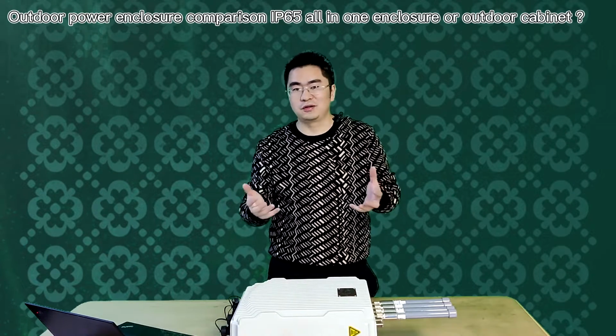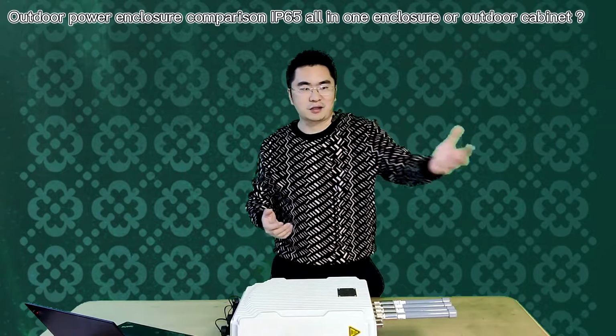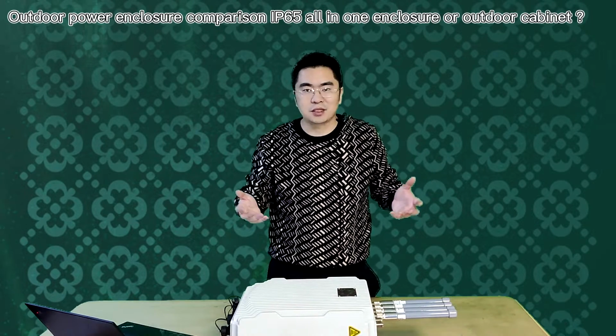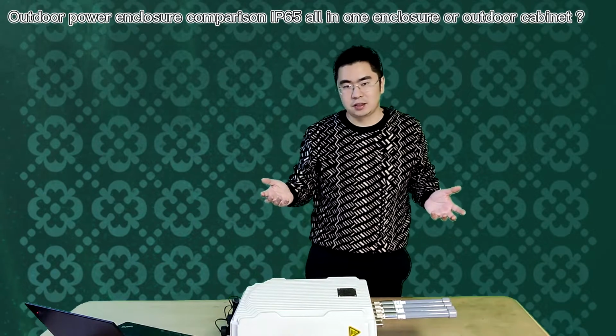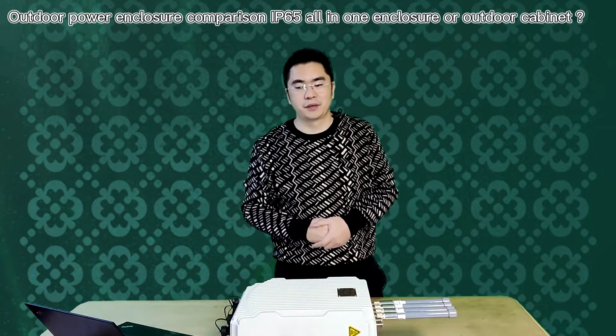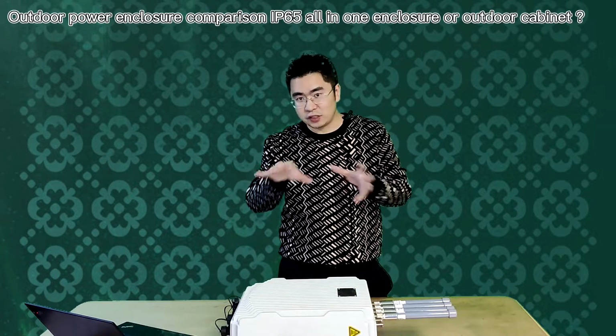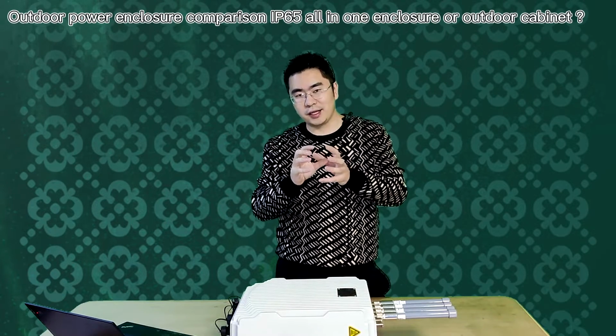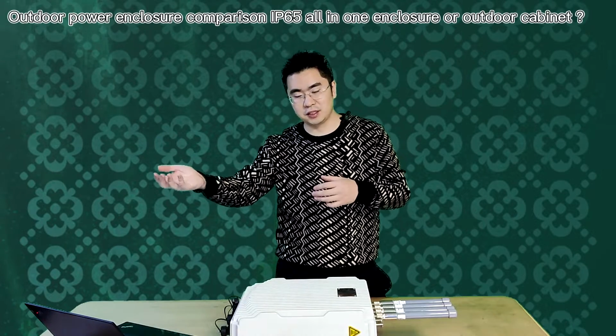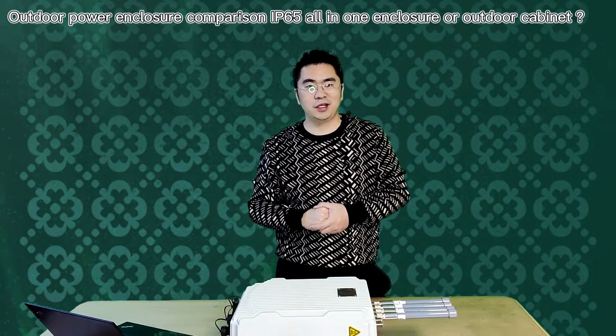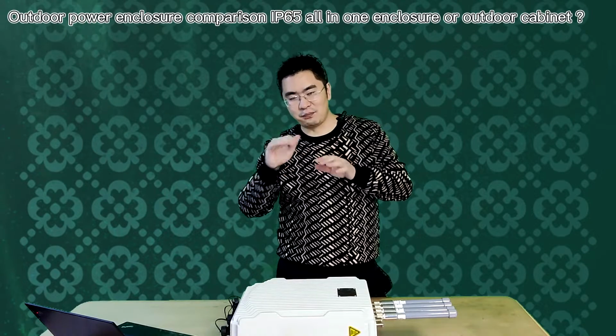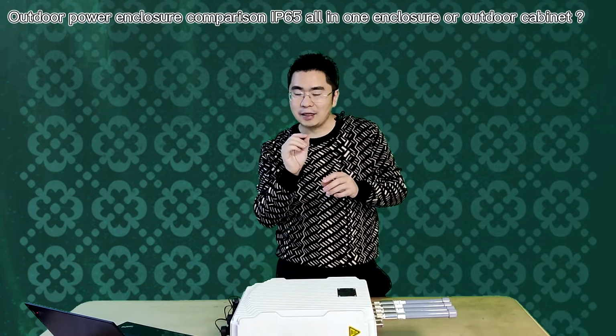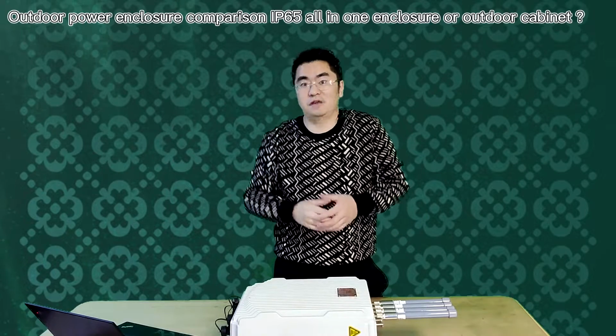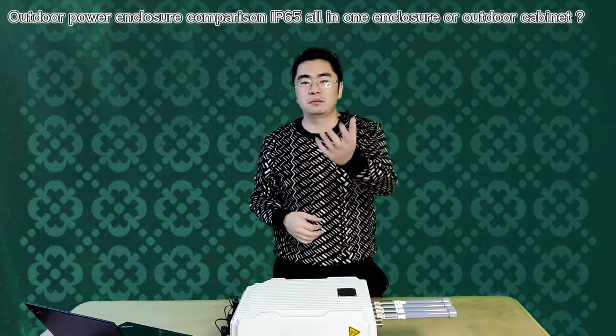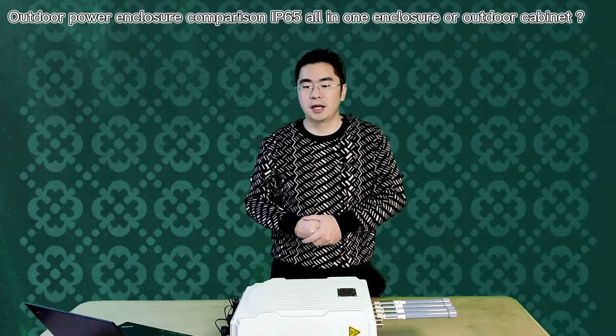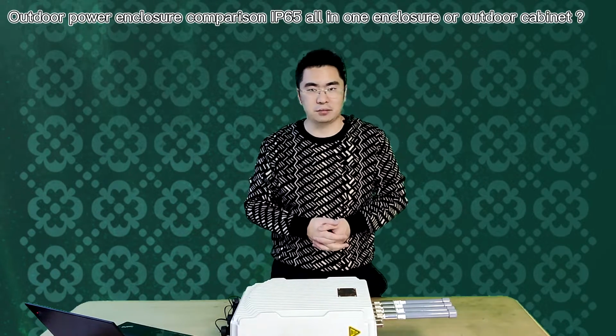But imagine that if you deploy this kind of site in whatever country, in the summertime, the temperature can easily be higher than 30 degrees centigrade. And the fan system cannot really cool down the system. The fan system can only exchange the air between the outside of the cabinet and the inside of the cabinet. So it can only make the temperature inside the cabinet a little bit higher than the environment. So if the environment is 30 degrees centigrade, you can imagine that you have 32 degrees centigrade. And then it's really harmful for the lead acid battery.